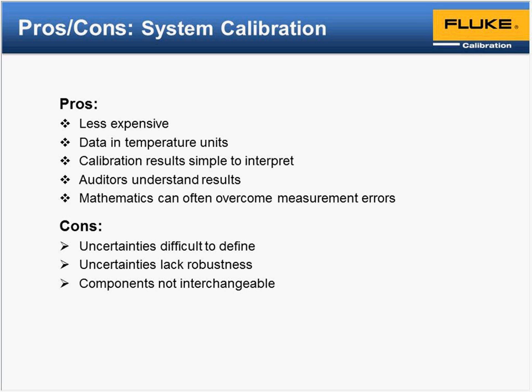The thing that's kind of a con is that you lack robustness. With a system calibration, it's really hard to define which piece is contributing to the error, because we're just nulling across the playing field, and we don't care if the error is coming from the probe or from the readout. We're just going to zero it, basically putting it into the electronics of the readout alone. So that's something to keep in mind as you go through the various types of actions that can be performed.